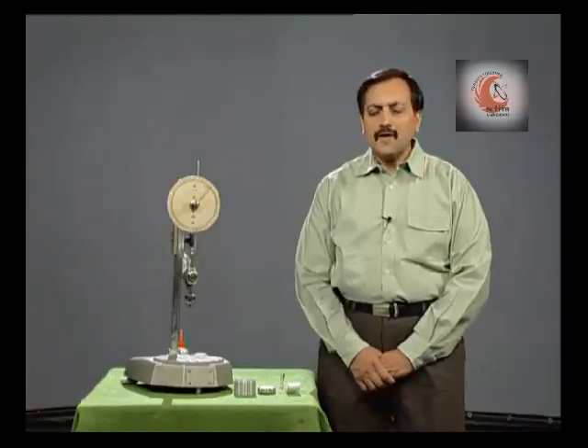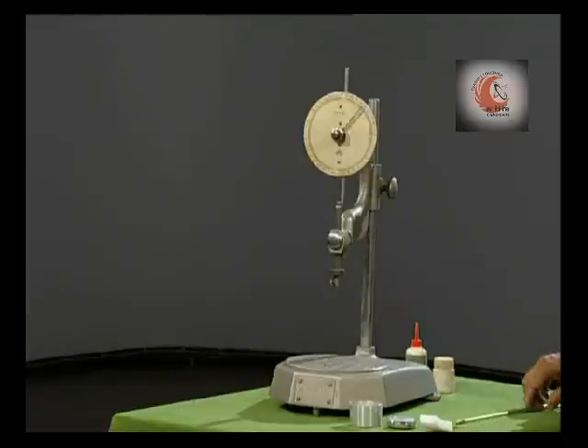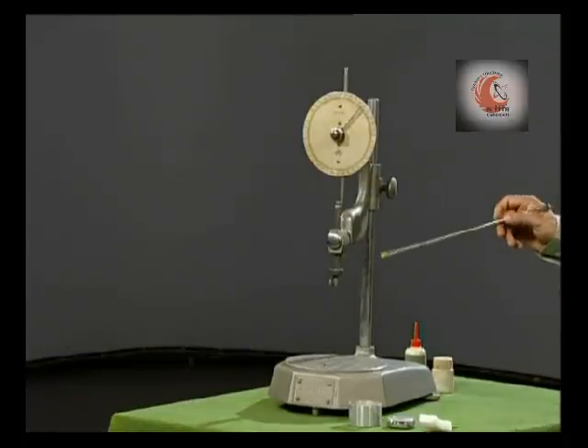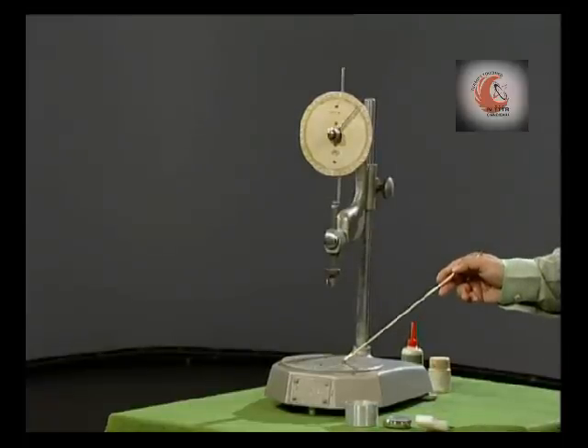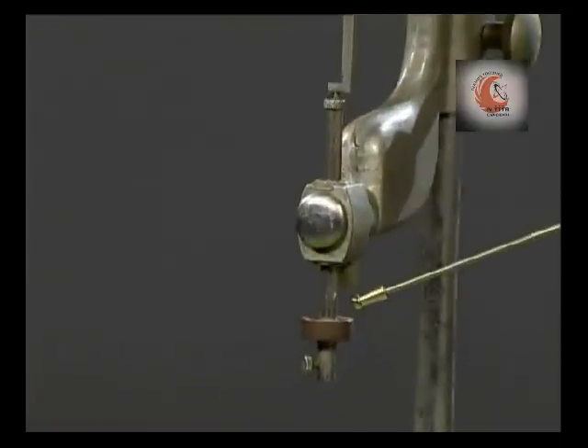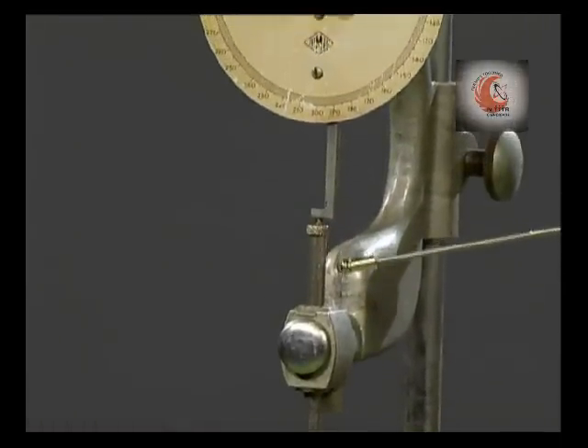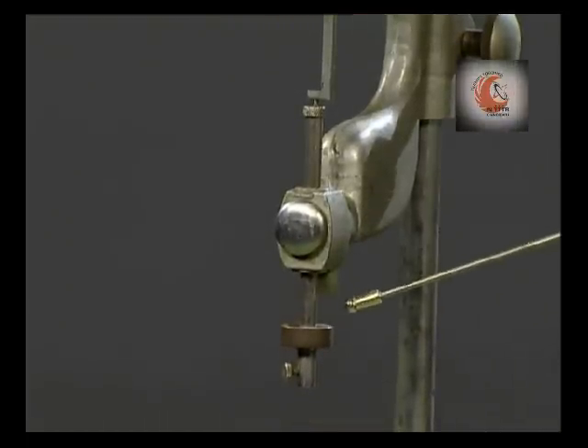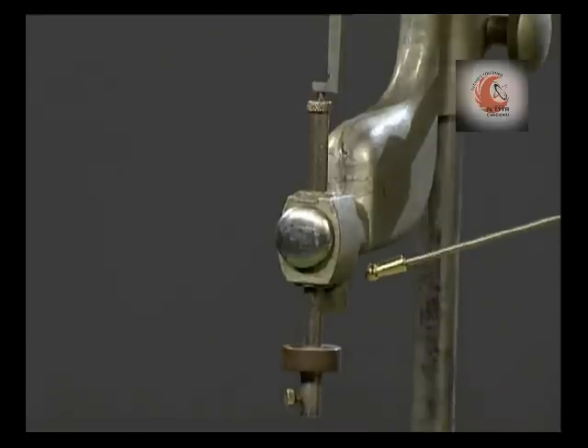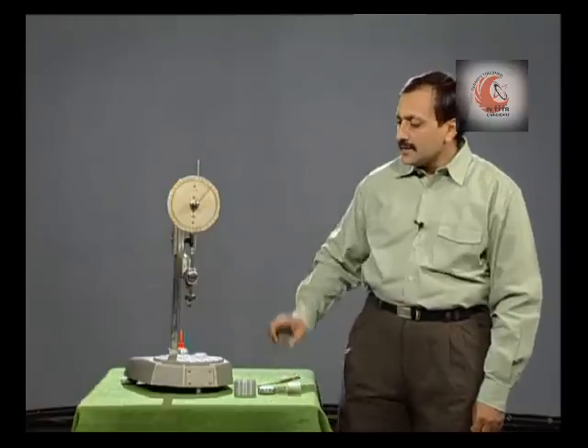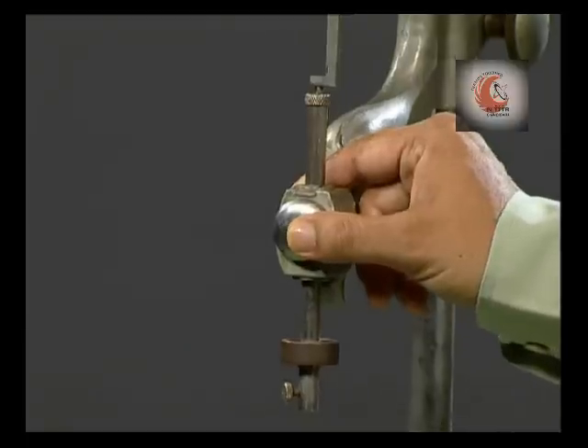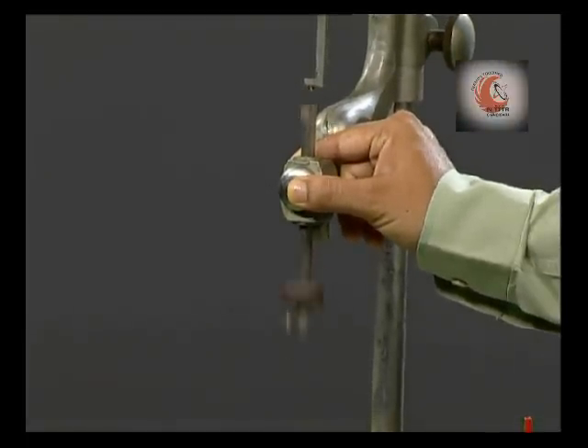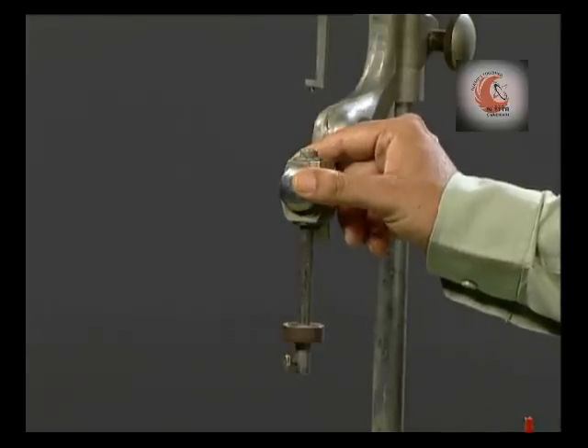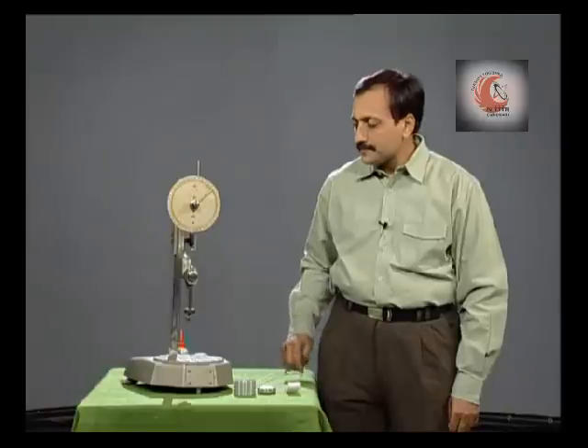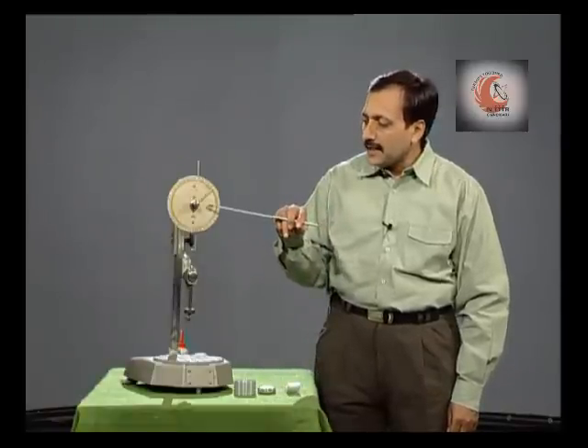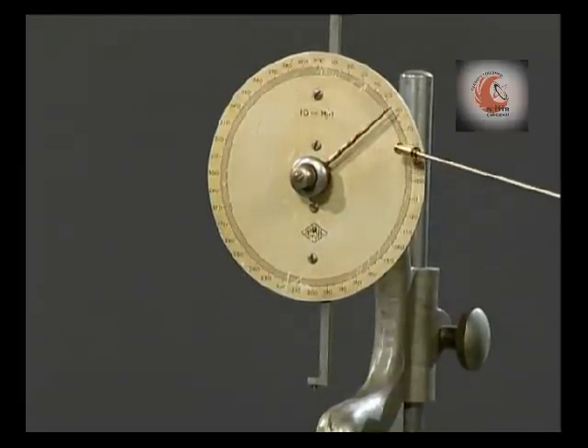We need a simple instrument called a penetrometer for this purpose. This is a manual type penetrometer. It comprises a metal base, a weight and a carrier. The total weight of this carrier assembly including that of the penetration needle is 100 grams. It has a release knob. As we push the knob, the assembly is released, and as we take out the pressure, it is locked again. At the top, we have a dial which is graduated in 1/10 of a millimeter.